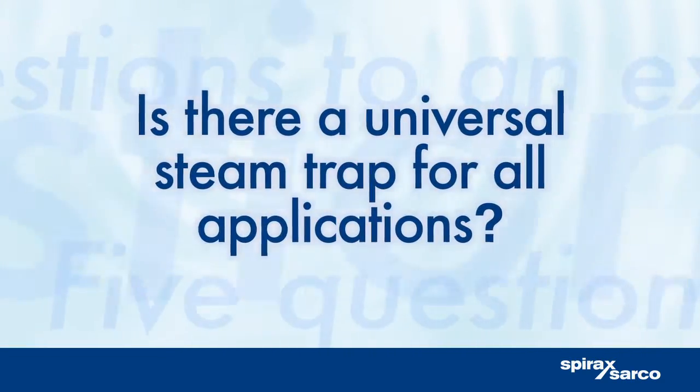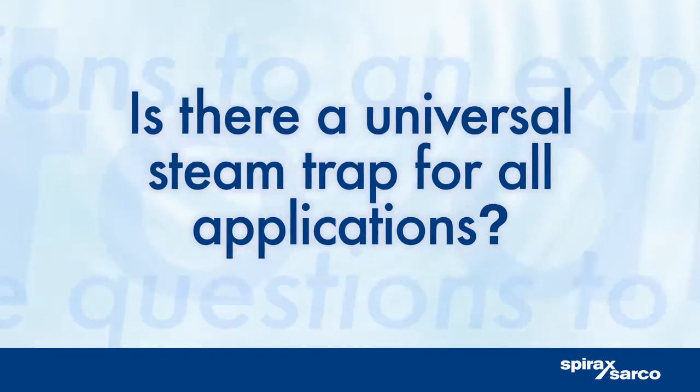Is there a universal steam trap for all applications? Not really. There are orifice traps that do claim to be universal, but they're only really suitable for steady-state applications. The trouble is the majority of applications have varying loads, so it's impossible to find one steam trap that suits all applications.